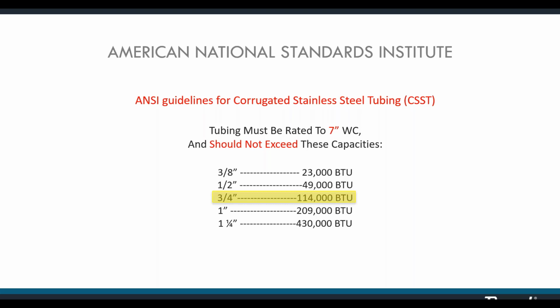But bear in mind, that thing's going to be a lot more expensive. It's going to be a lot less flexible. You know, that little 1/4 inch, 3/4 inch, whatever you got, you whip that thing around like a toy. All right. At 1.25 inch, it's going to be a lot harder to bend. It's going to be a lot less flexible for tight turns. It's just going to be less convenient. We're going to recommend using rigid pipe right up to the gas valve.